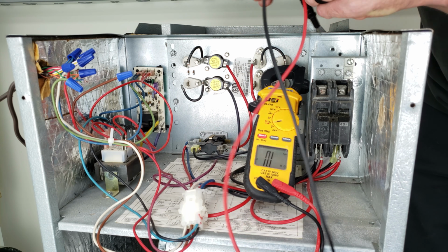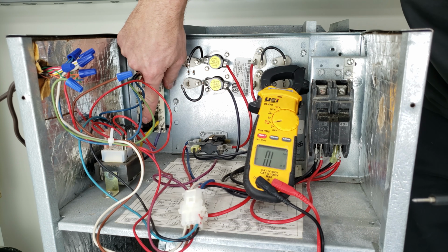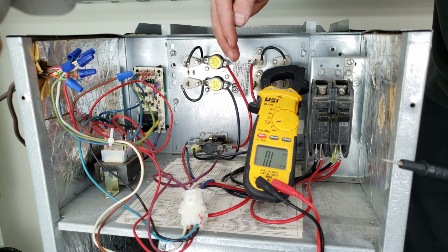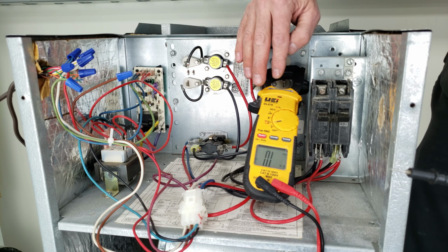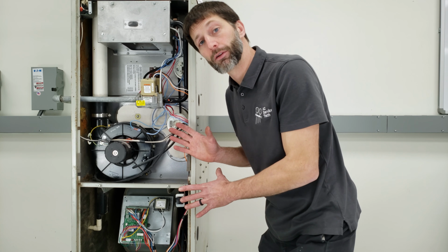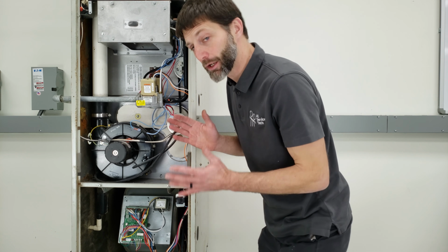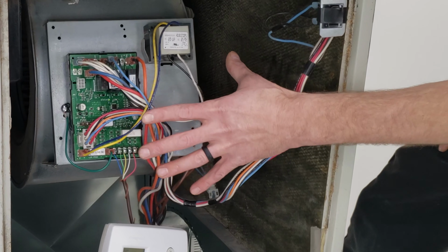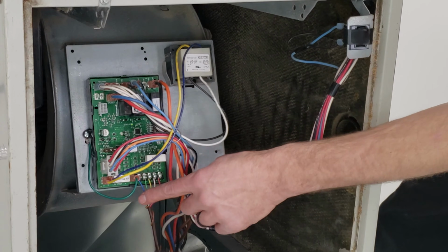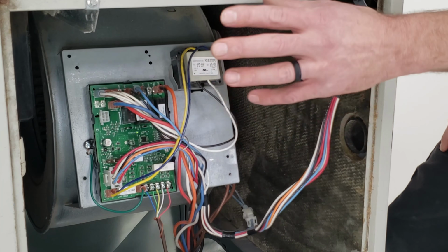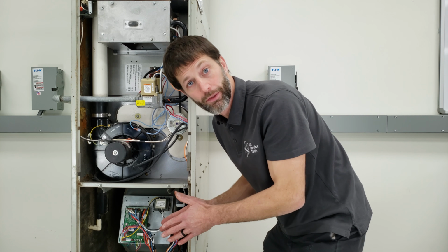So you could check this with a voltage across from here to here, or across a switch. So there's multiple different ways in order to check switches, and you can check out another video I have on measuring electrical switches. Furnaces are a little different than air handlers as far as what the intermittent problem could be. You could have the same type of thing. You could have a high electrical resistance problem, either with thermostat wires or your high voltage wiring or your connection or your contacts. That's certainly one thing.